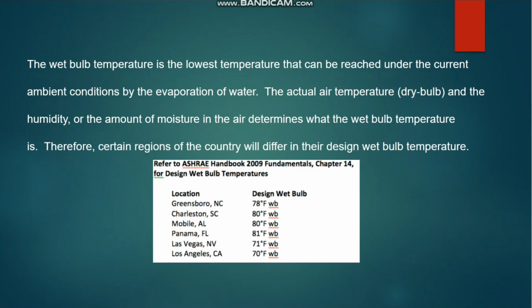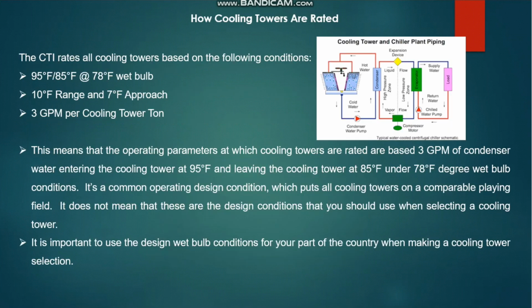For example, you can see the ASHRAE Application Handbook, chapter 14 from the 2009 Fundamentals, that the wet bulb temperature is different for different United States regions, like Los Angeles 70 degrees Fahrenheit, Las Vegas 71 degrees Fahrenheit, and different locations have different wet bulb temperatures. So the cooling tower selection must be done based on the wet bulb temperature.